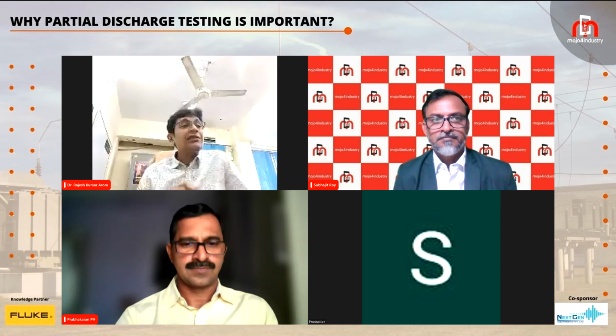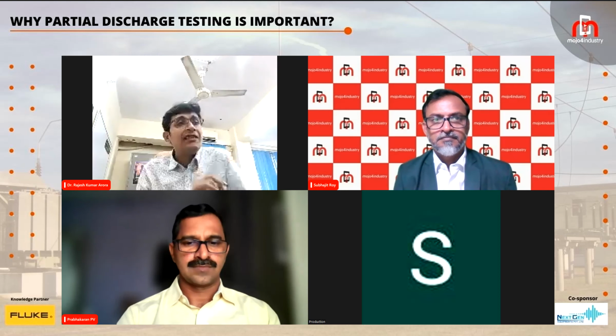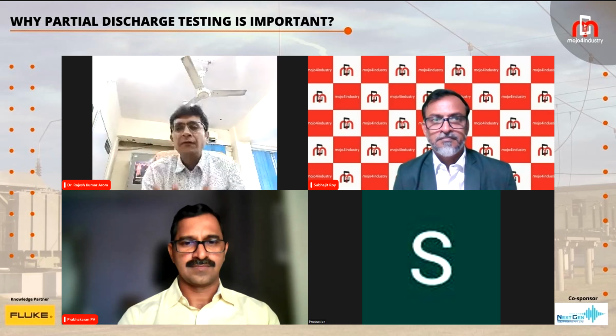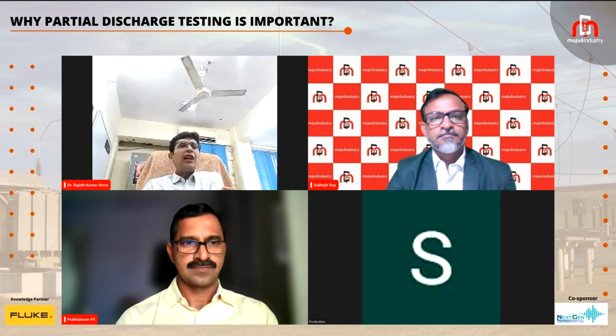Coming to the factors and reasons resulting in PDs. The very first reason for PD in any equipment is the design. We start everything with a design, and after design, it goes to production. After production, the equipment goes into transportation. And after transportation, the commissioning starts. And after commissioning, severe service conditions may cause partial discharge. This is all about the factors resulting in partial discharge for any equipment. Now, coming to why partial discharge testing. It is required, it is good, it is mandatory to check the insulation imperfection, to check the dielectric integrity. It is important to go for that partial discharge testing.